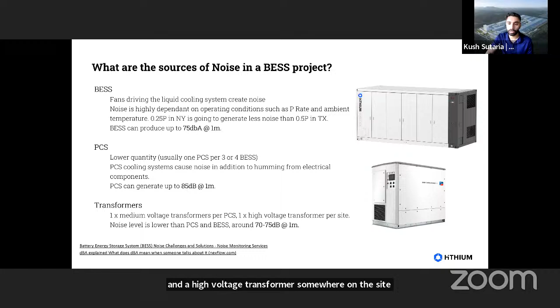Transformers again can produce some electrical noise, and you'll generally have 1 medium voltage transformer per PCS and a high voltage transformer somewhere on the site, but that's less of a concern. Some of these are site-wide strategies, and others are BESS specific.